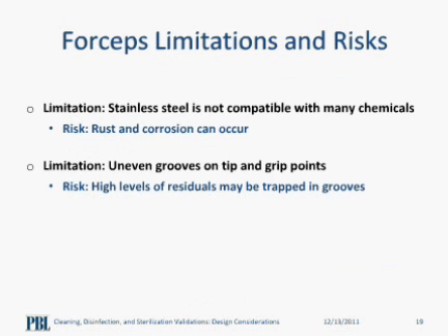Surgical forceps may be simple, but they can cause validation problems. While high-level disinfectants can render the forceps sterile, many chemicals are not compatible with the stainless steel. They can cause rust and corrosion. Another thing to point out are the uneven grooves on the tip and grip points of the forceps. These grooves can trap unacceptable levels of residuals or contaminants.